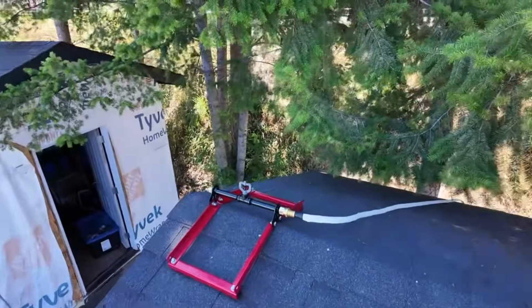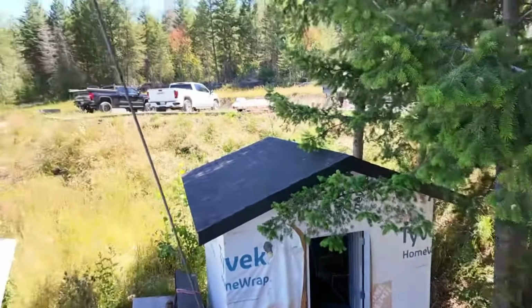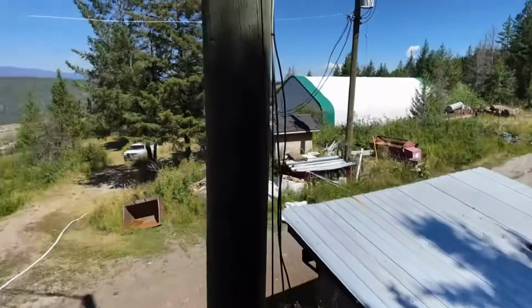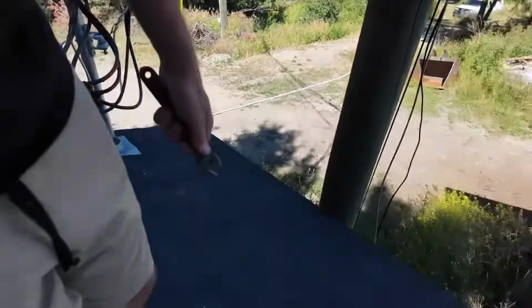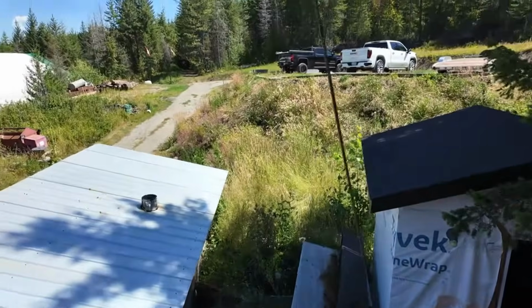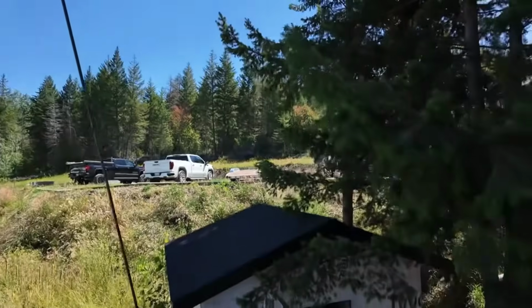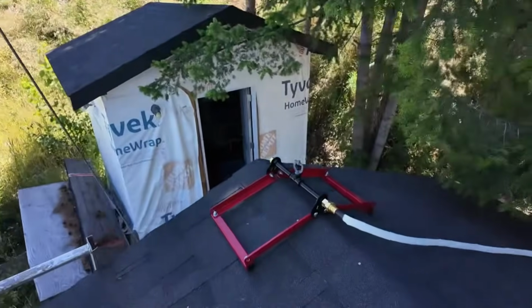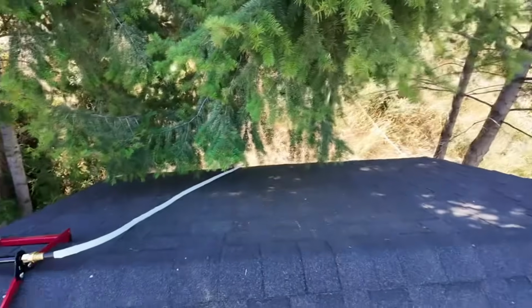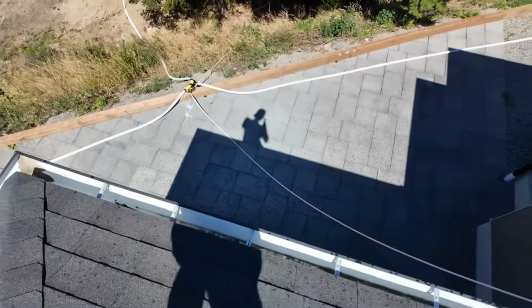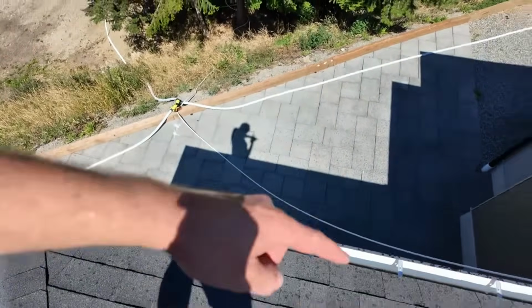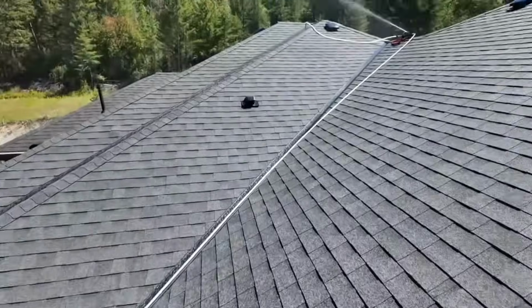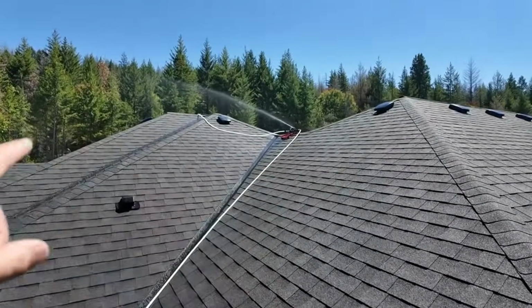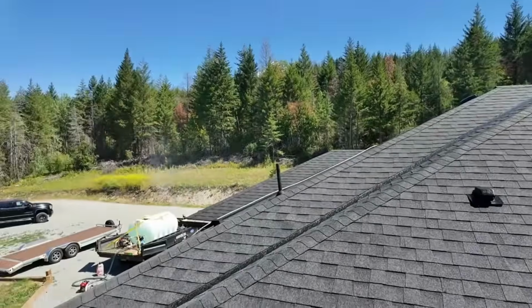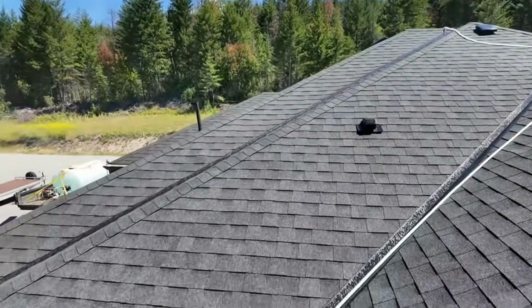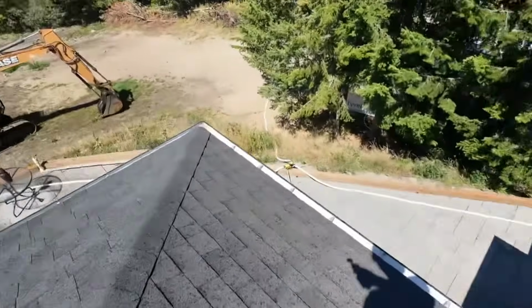So we've got one roof peak to protect these 3 buildings. We're standing on an electrical room, water room, boiler room. This will give us a nice 60-foot diameter. So up on the roof here now, that line comes up to the roof peak, and that peak goes down to 2 gutters. What you're looking for is even water droplets across the whole roof, which is what we have.